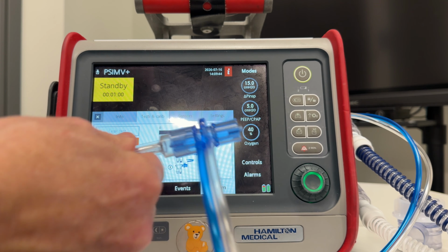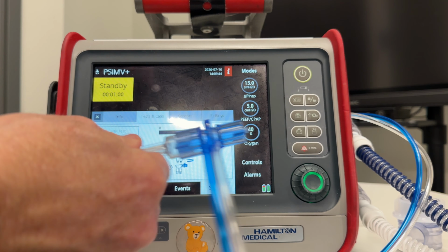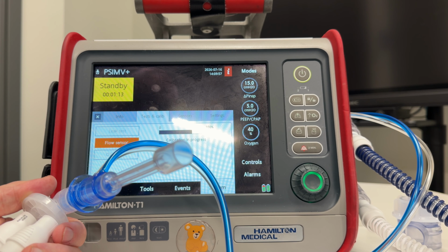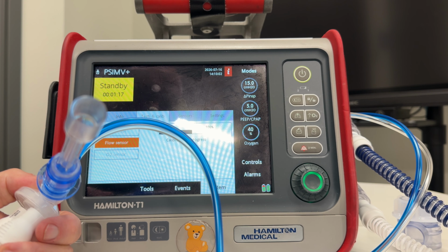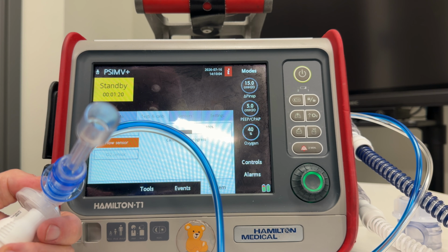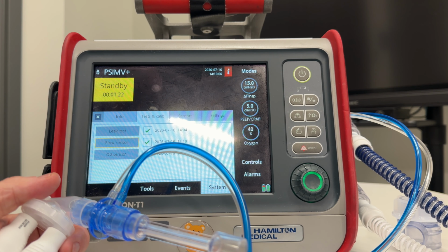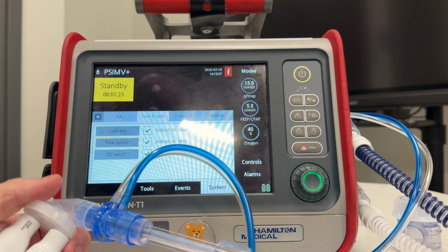It tells you to turn the flow sensor again. You'll just flip it around. It's going to go through the same process. And I already know it's going to pass because it went through that ramp up stage. All right, we get the green check mark. So with that being said, this flow sensor or this circuit is ready to go on this pediatric exhaust valve.